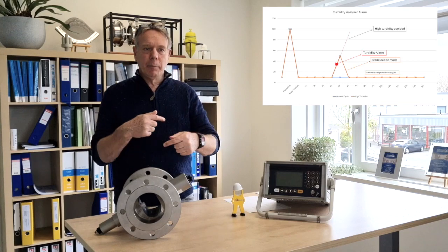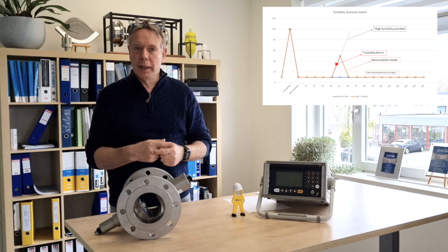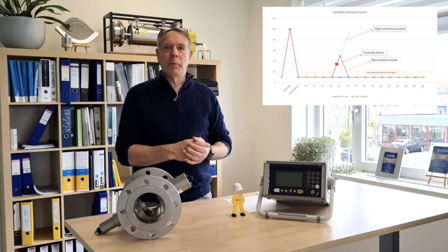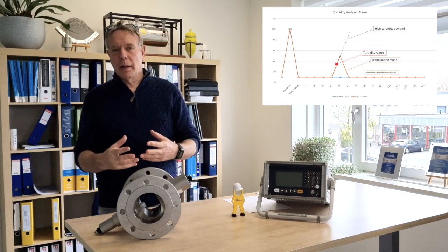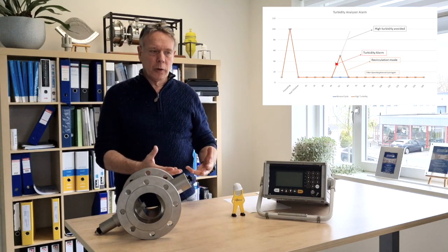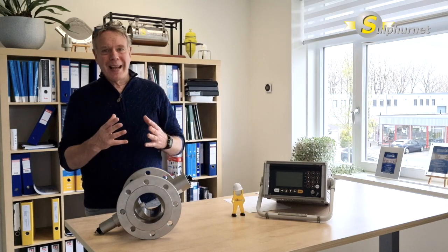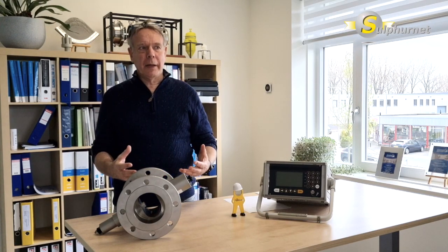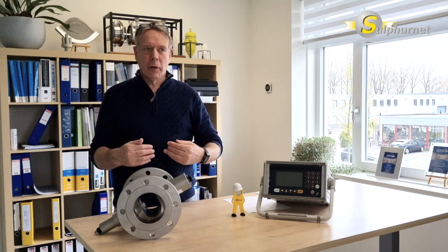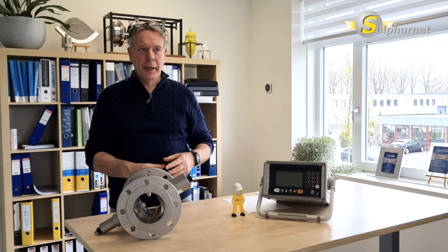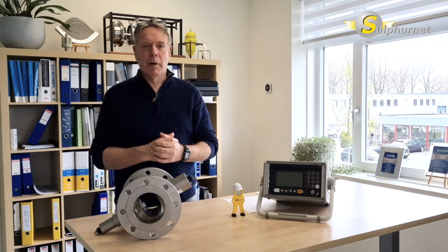Either you can put the filter in a circulation loop, or you can stop the filtration process and you can decide to clean the filter and find out what the cause is of the ash leakages. This way you protect your catalyst bed and you prevent all the solids getting into the first catalyst bed, meaning you increase the lifetime of the acid plant.